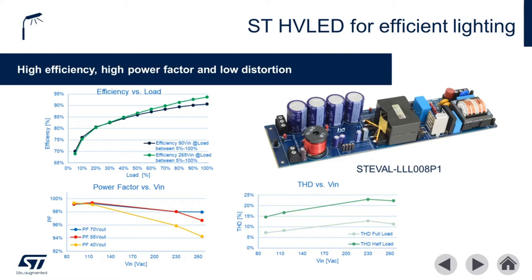At 90 percent load the solution provides a total efficiency of 90 percent, and power factor exceeds 94 percent across all input voltage and output voltage ranges. At full load THD is below 15 percent, and even at half load THD is below 25 percent across the full input voltage range.